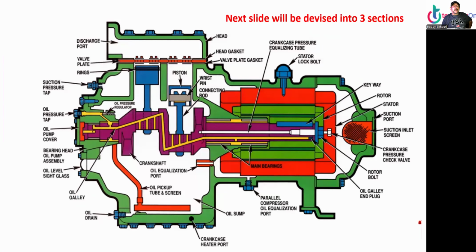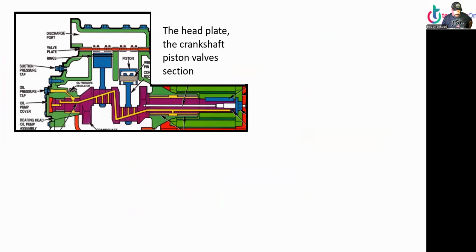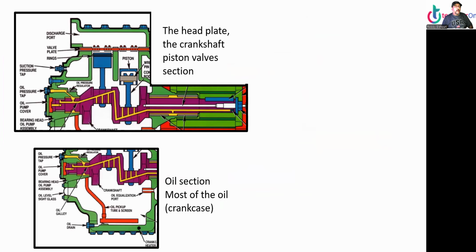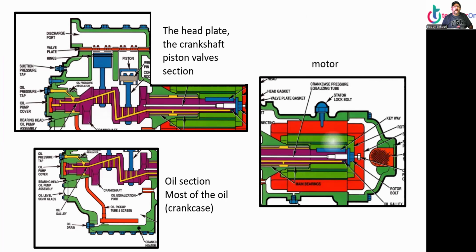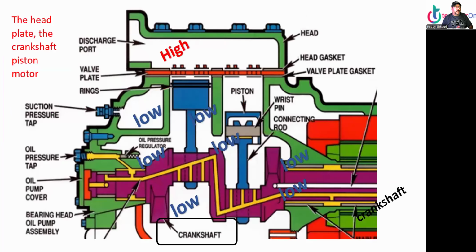Now, this next slide, I'll divide this one into 3 sections. The head plate, the crank head plate, crankshaft, piston valve section, oil section, most of the oil in the crankcase, and the motor section. Alrighty. The head plate, the crankshaft piston is the high pressure. The whole body is low pressure. The only thing high is on top. Everything else is low. All right, we have the discharge port and the head are high pressure.